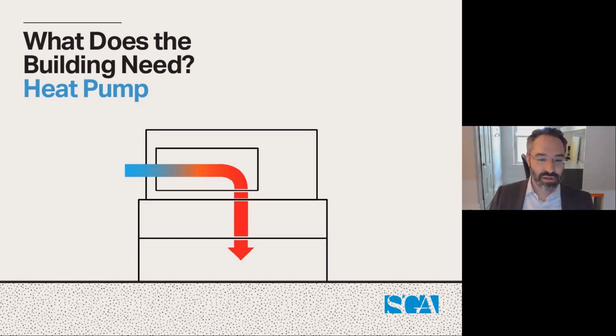With a heat pump, you're not turning electricity into heat, you're using electricity to move heat. So you can get a coefficient of performance of 3 or 4 or higher. The bigger your heat pump, the more efficient it is. There are grid scale heat pumps in Europe getting a coefficient of performance of 8 or 9, meaning for every watt you spend on electricity, you get 8 or 9 watts of heat in your building. At a building scale, we're probably talking in the 5 or 6 range. It's still really good, you're multiplying that energy by 5 or 6 times.